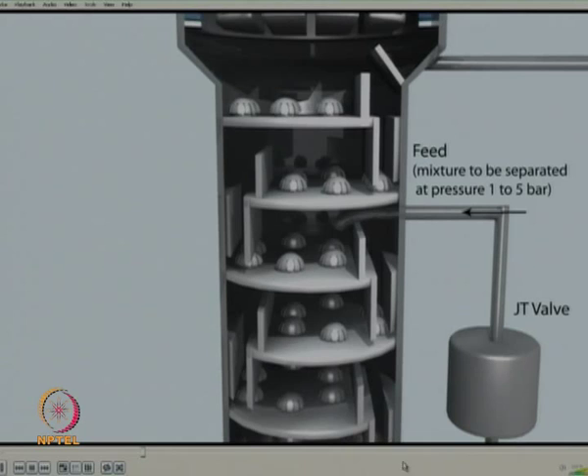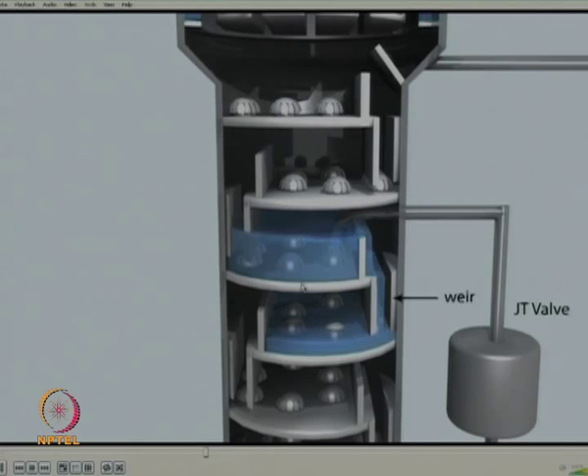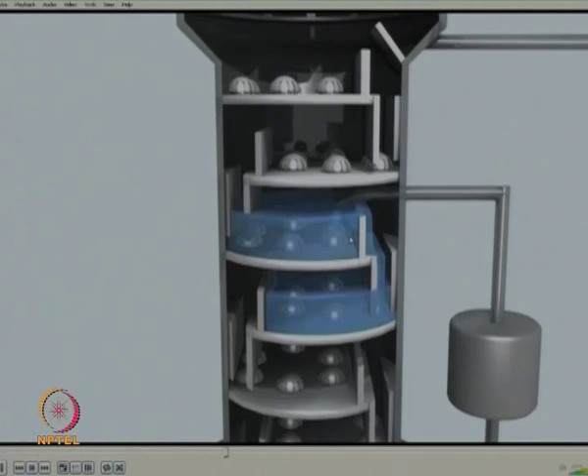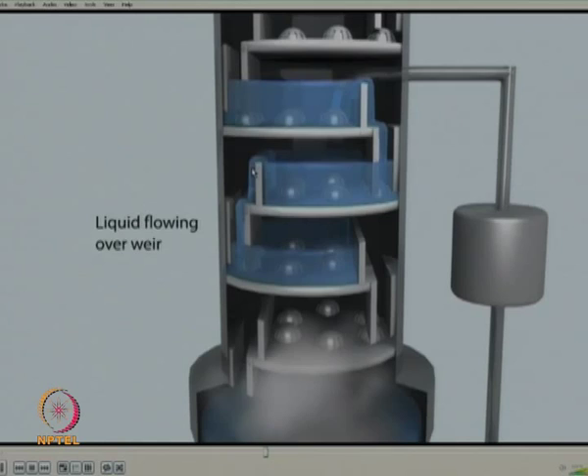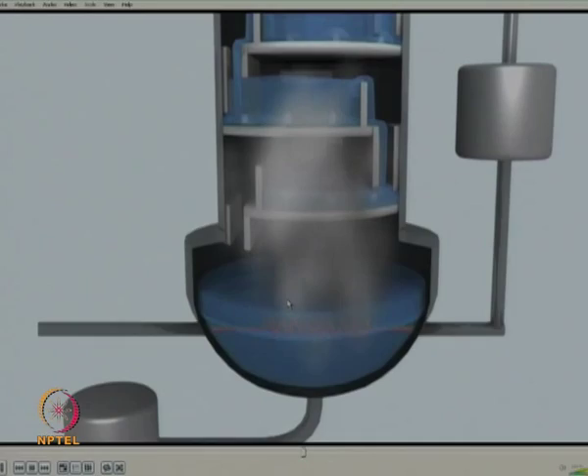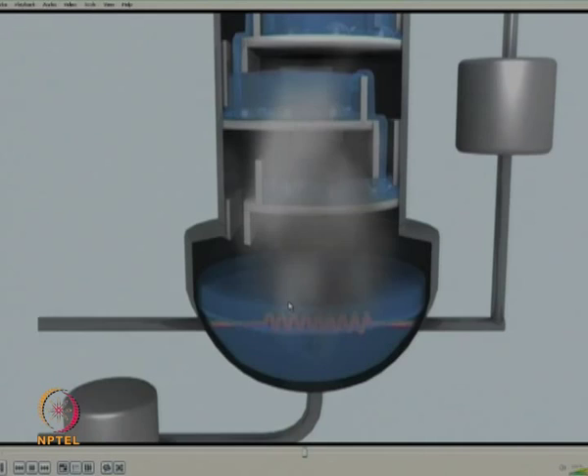During pre-cooling, some vapors get evaporated and start rising up. The process gas then gets expanded through a Joule-Thomson valve and enters at the middle of the column. The liquid starts accumulating on the plates, and once the liquid level reaches a certain height it starts coming down to the next plate below. As each plate fills up to the weir height, liquid comes down and vapor rises from the bottom.